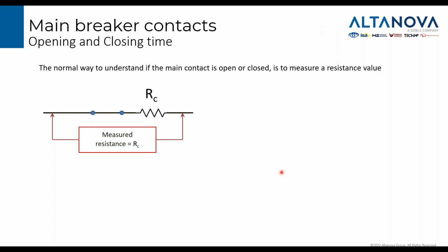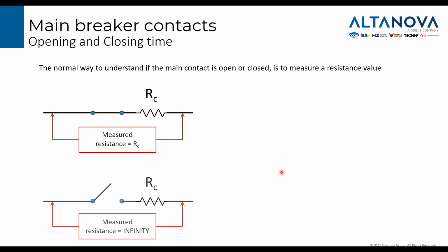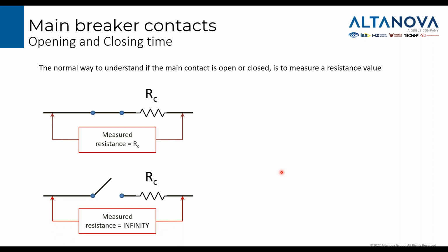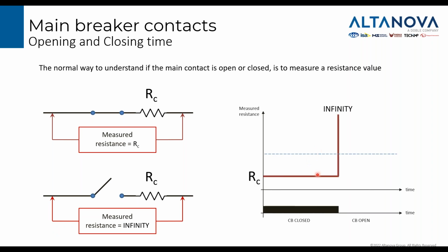The normal way to understand if the main contact is open or closed is to measure a resistance value. When the circuit breaker is closed, the value of the resistance is extremely low. And when it is open, this resistance tends to go to infinity. So if we are able to detect the moment where this value changes, from a very low value to a very high value, we are able to understand when the circuit breaker is closed and when it is open.